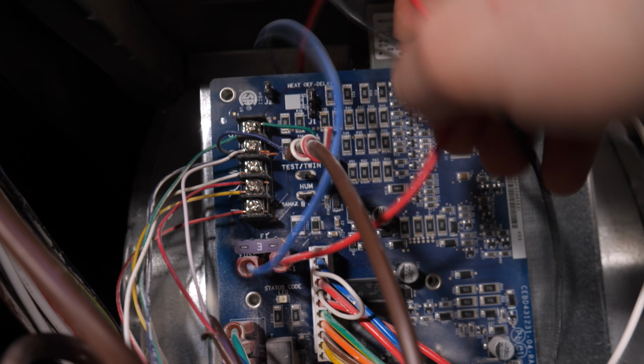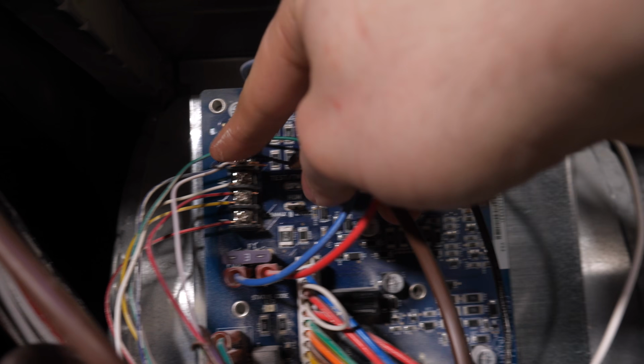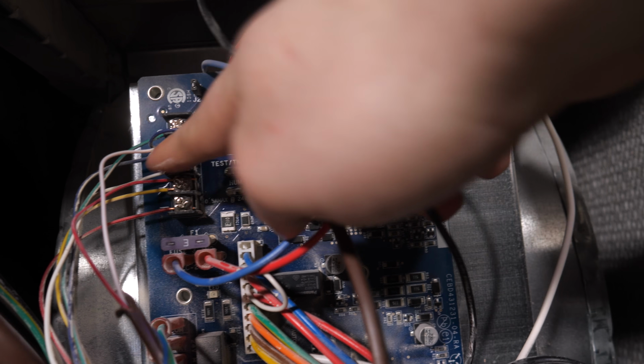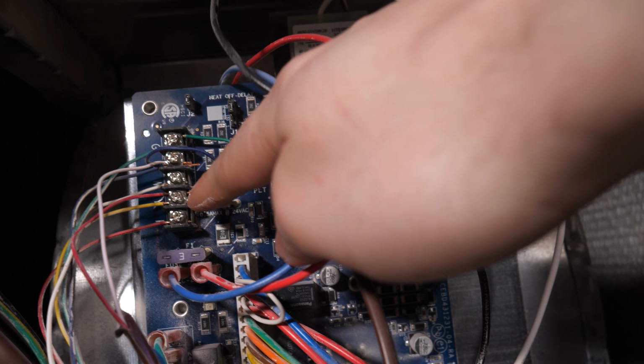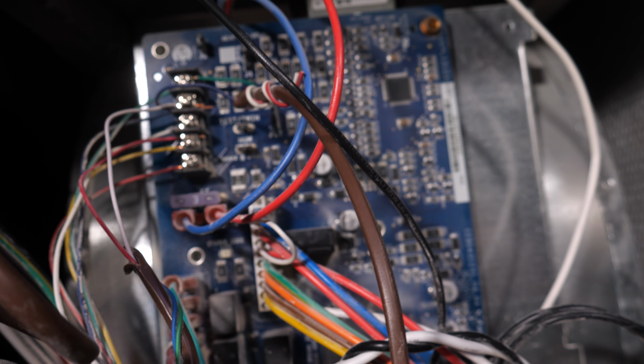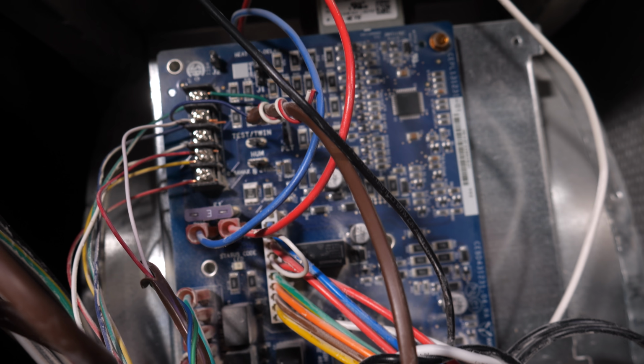This ultimately means if you wire that water valve across the common wire and the heat signal wire coming from the thermostat, then the humidifier will only be able to operate when your thermostat is calling for heat. This setup not only ensures the blower will be running when the humidifier is on, but it also means the humidifier won't run during a cooling call. So if you forget to switch it off at the end of the heating season, it's no big deal.